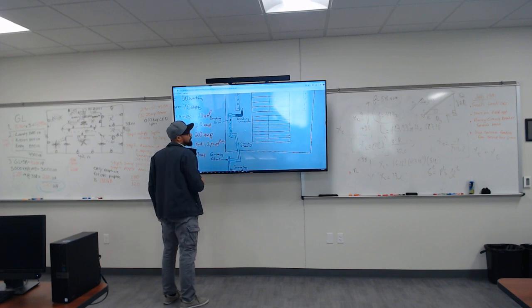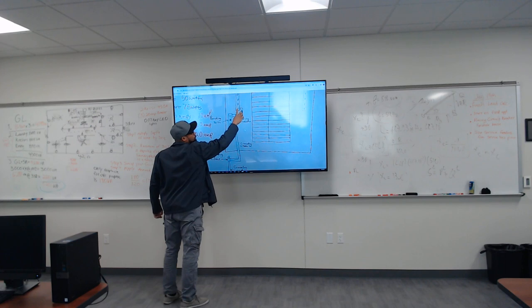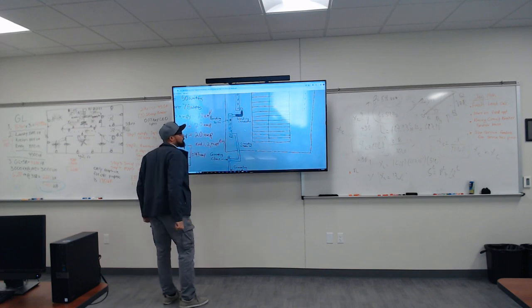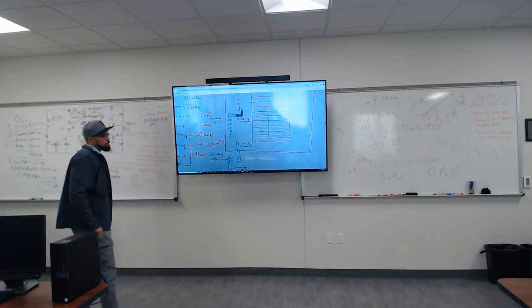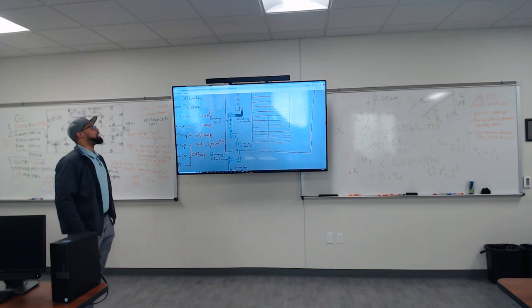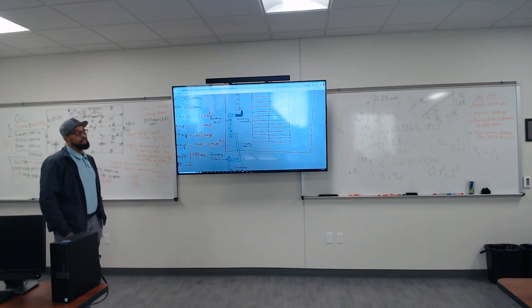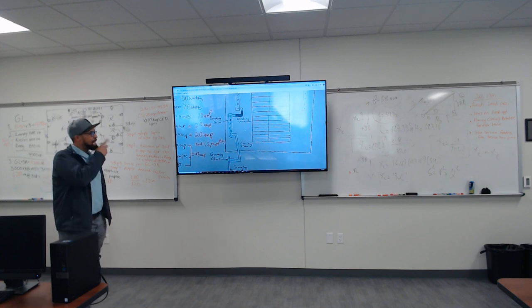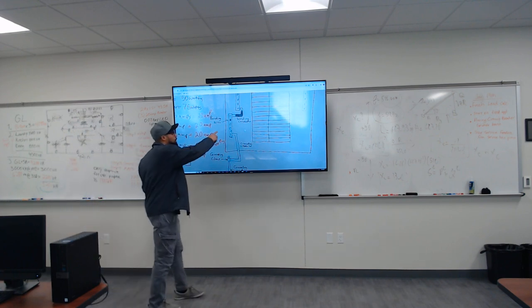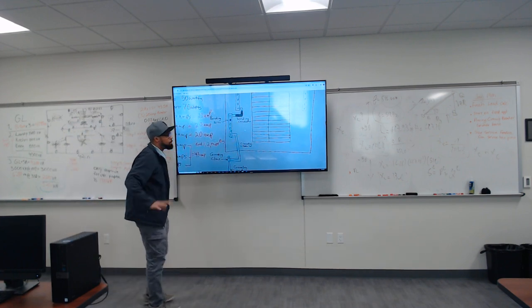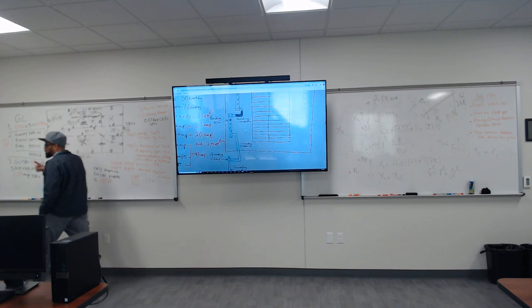You have a bonding screw. That is required. That is code. This conductor, this is the neutral bus bar. That right there is the bonding conductor. And I know in Article 250, which is the biggest article, I gotta go find it, but I know off the top of my head that that size conductor should be 4 gauge, nothing left. But let's go find it. I have to find it so you all can help me.